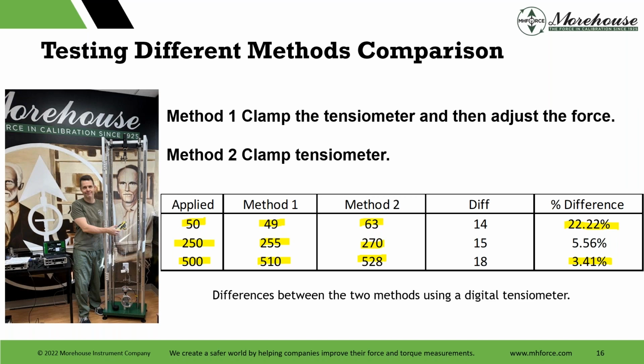And I wanted to make a note here that this test used digital tensiometers, which do not typically introduce as much internal tension as some of the analog ones. It is a much softer grip if anybody's used the digital tensiometers. Like I said, we do not calibrate or sell actual tensiometers, just the equipment to calibrate them, like the load cell. We sell cable sets and the machine. So using these different tensiometers, I can have my biased opinion on them, and I can tell you that I would prefer the digital ones. By far, I prefer them to the analog ones. I think they're so much better. They introduce less tension.